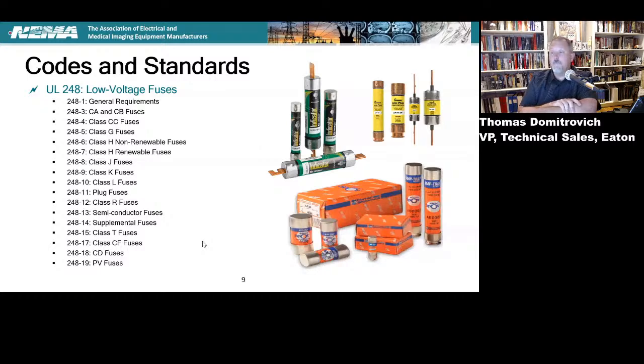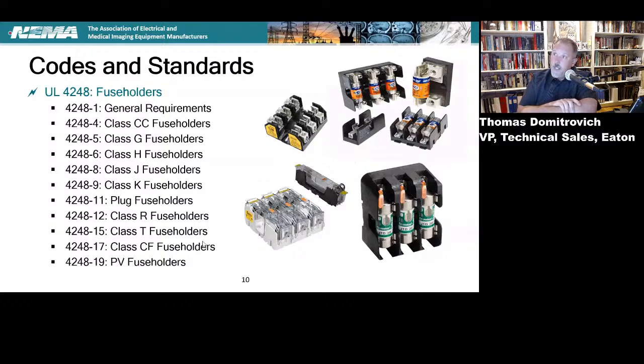And on another note, here are your fuse holders, following the same guidelines as the fuses themselves. If you think about it, a circuit breaker is all enclosed, so it has the switch inside and the overcurrent protection capabilities, but a fuse is separate from its holder. So we have to have standards to help the marriage between the fuse itself and its holder to achieve its function in whatever circuit and whatever piece of equipment you're putting it into.